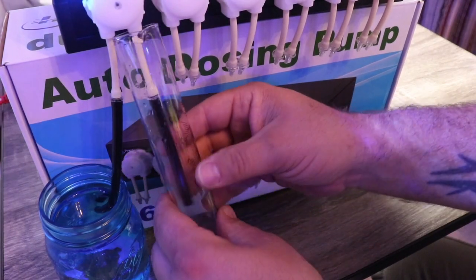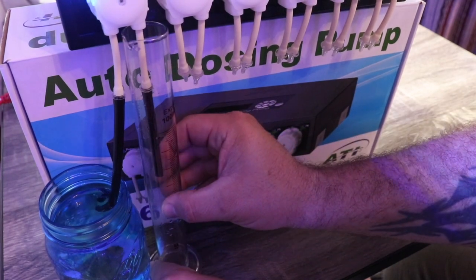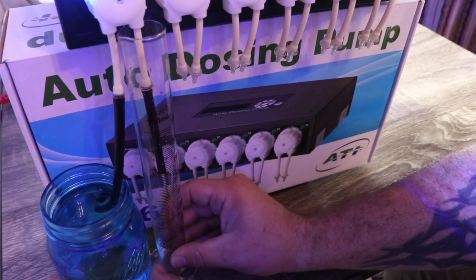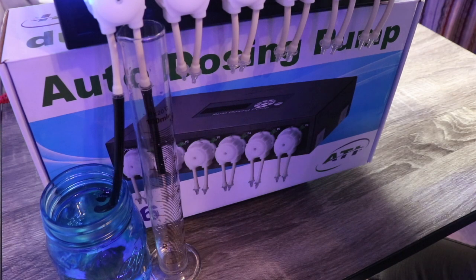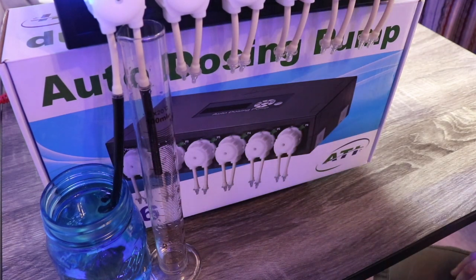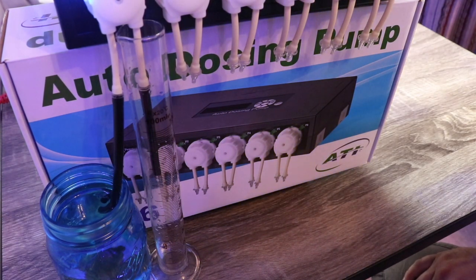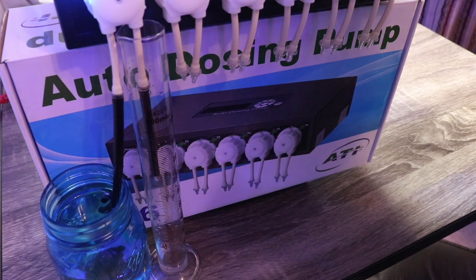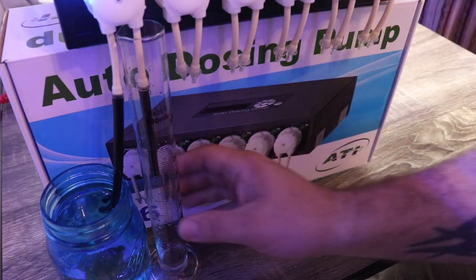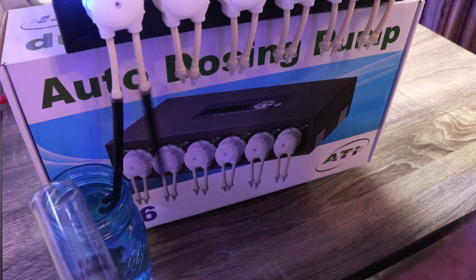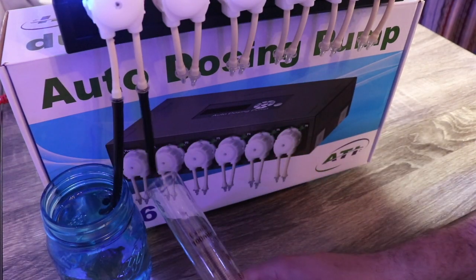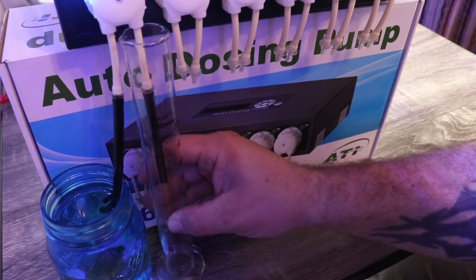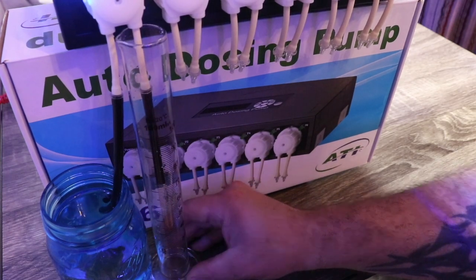So as far as calibrating the auto dosing pump, it is relatively easy to do. You do need a graduated cylinder, which is not included. They are relatively inexpensive to pick up, and they are pretty handy to have around, especially when you start getting into dosing. With this device, it's important to make sure that you prime the lines prior to doing any type of calibration. You want to make sure that there's no air that is possibly going to offset the measurement.